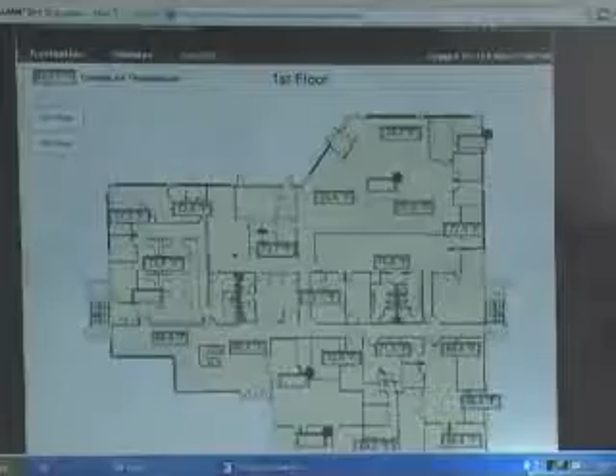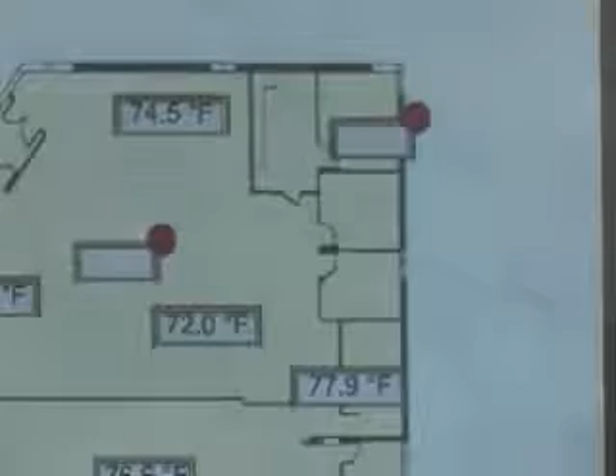I've got a couple of reds here. What are those, alarms? Right now those reds are what we affectionately call blisters, or the measles. Those are VAV boxes that have probably gone offline. Since we brought the building automation system online and can see the whole system, we've discovered some mechanical problems with the VAV boxes themselves.